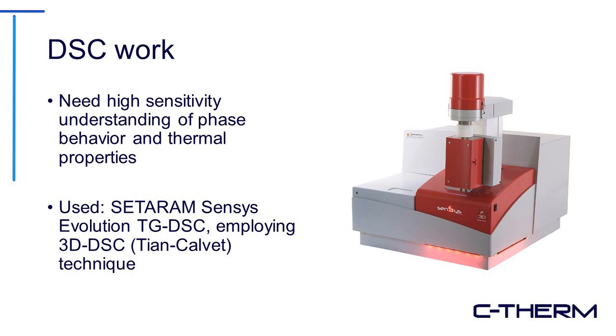And the cylindrical heat flow sensor has a number of different advantages to it. The biggest one is that it can detect both convection and radiation in addition to thermal conduction, whereas a traditional flat pan-style DSC is only able to detect thermal conduction down into the sensor. This kind of heat flow sensor winds up being much more sensitive to small heat effects, as the overall heat flow sensor efficiency is in excess of 90%, whereas with a traditional heat flux DSC, the sensor efficiency is going to be on the order of 35 to 40% at best.